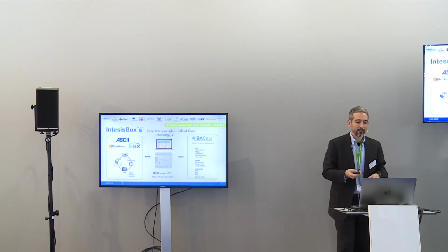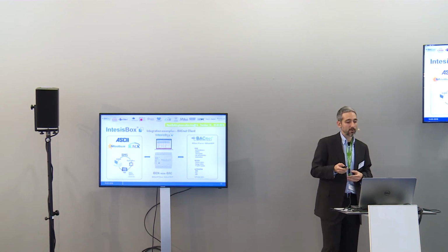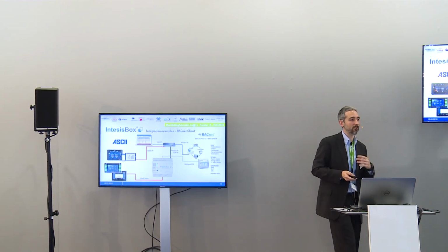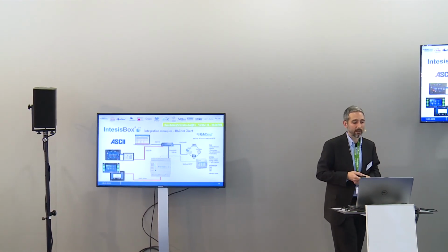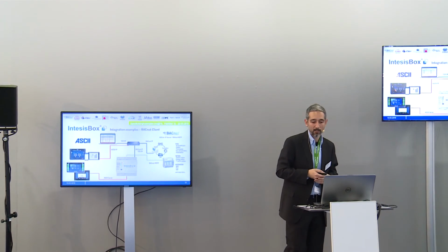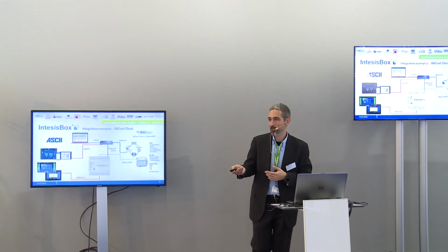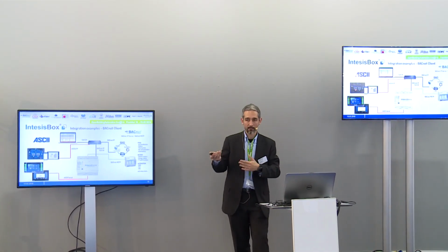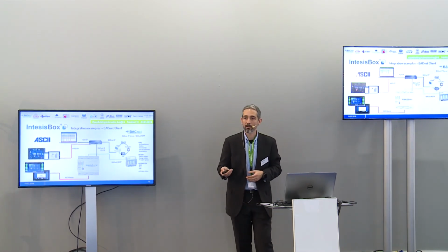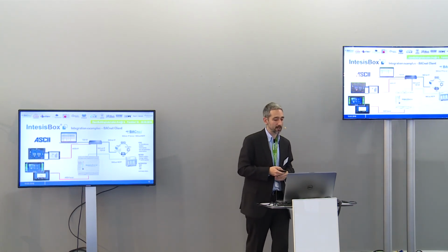Okay, and now just the other way around. Now our box is acting as a BACnet client. In this case, we offer integration from other systems to BACnet devices. Imagine they have a room control based system, like a Crestron controller, AMX controller, or Extron controllers. You can connect to our box, and then connect to other systems that offer a BACnet server interface, maybe some BMS that has this role as well of a BACnet server, or some BACnet MSTP controllers, HVAC systems, this kind of stuff.